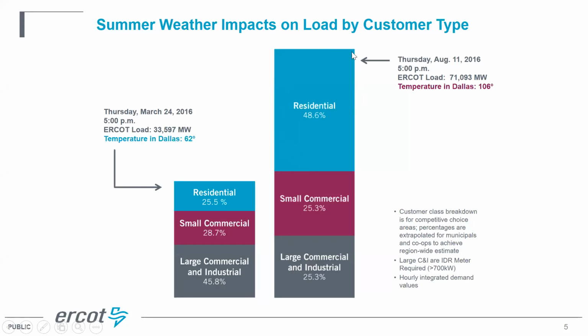If all of this was properly sized equipment that was running all day, running 20 hours of the 24 hours, while equipment's running, it pulls a whole lot less load than when it's starting and stopping and starting and stopping. So you're not only helping the single mom or the little old couple on a fixed income, you're also helping your state. And it really should be at very little or no cost to the builder, because that offset in the less expensive, smaller equipment can be more than offset by a proper design. So that's my spiel. I know y'all have heard it before, but I'm going to keep saying it until I talk every single jurisdiction in the state of Texas into swapping over.